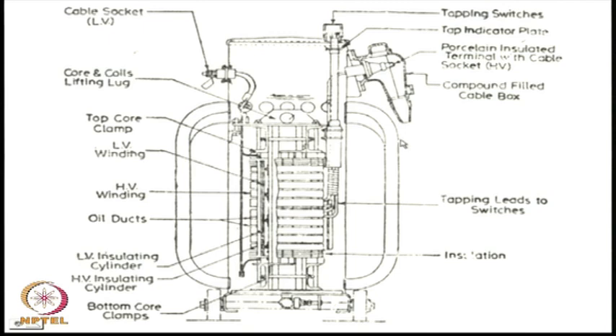So, here we can see the final assembly of a 3-phase transformer. The different parts are, this is the transformer tank which is visible from outside, these are the cooling pipes, these are the cooling pipes. Inside this tank, this is the oil level, this is the actual core and winding configuration.